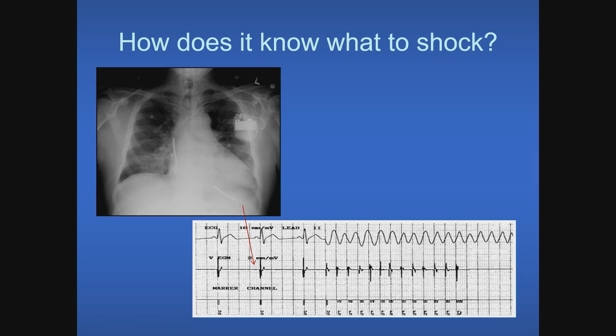There are actually two ways that the device can get the patient out of their arrhythmia. It can either charge up the capacitors and shock the patient, which can potentially be painful if the patient is still awake, or it can deliver paced impulses that are just a little bit faster than the sensed arrhythmia, called anti-tachycardia pacing, and that can get the patient out of their arrhythmia as well.